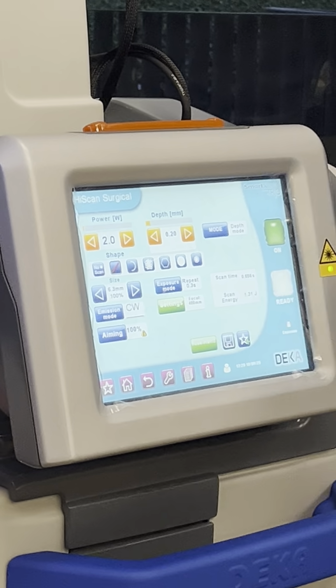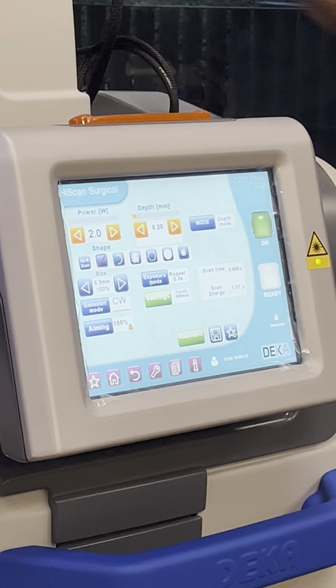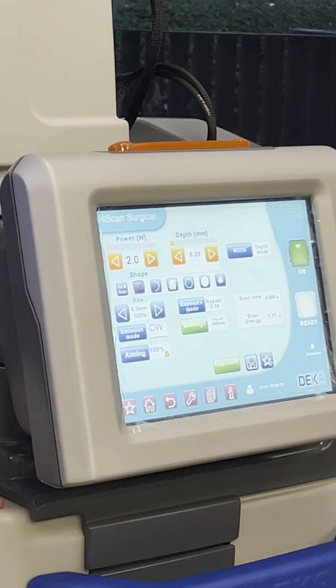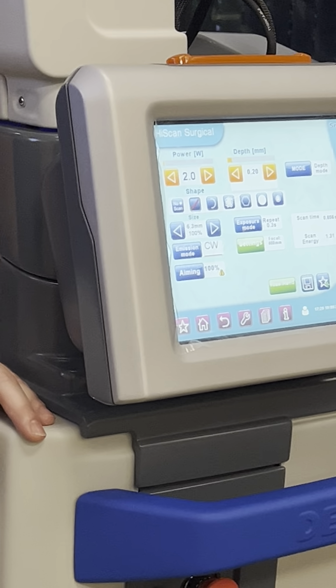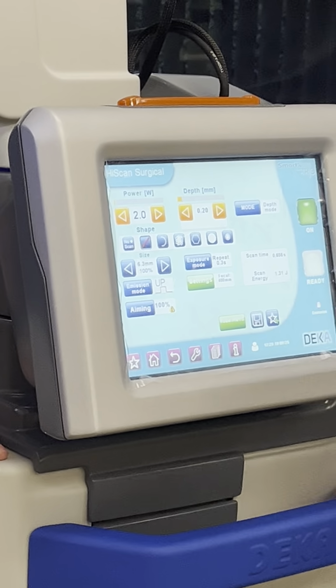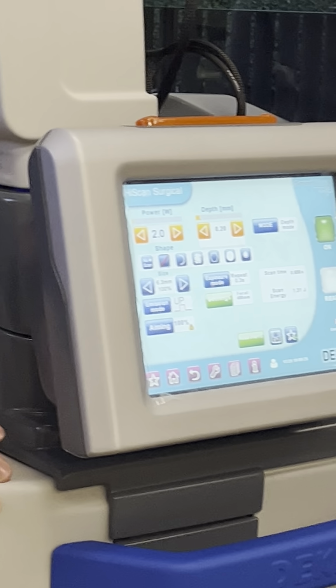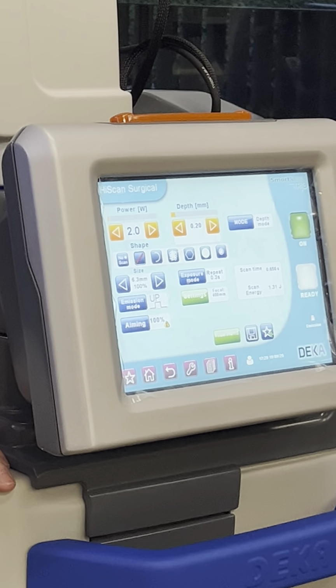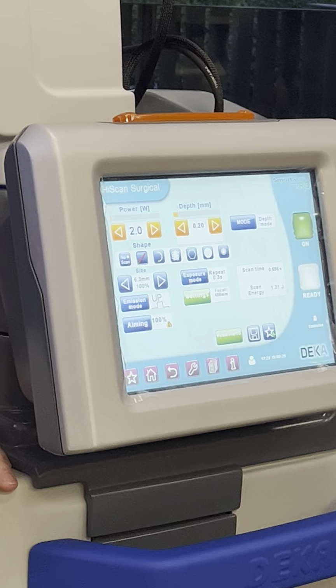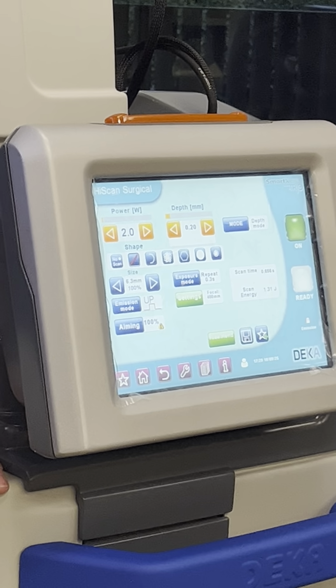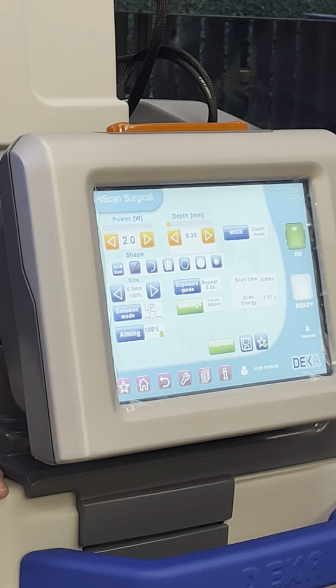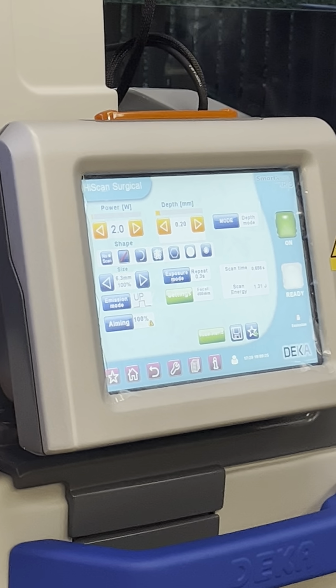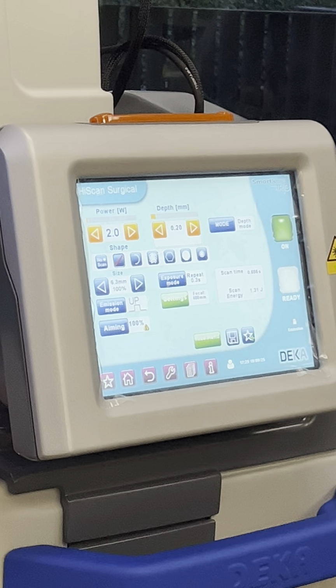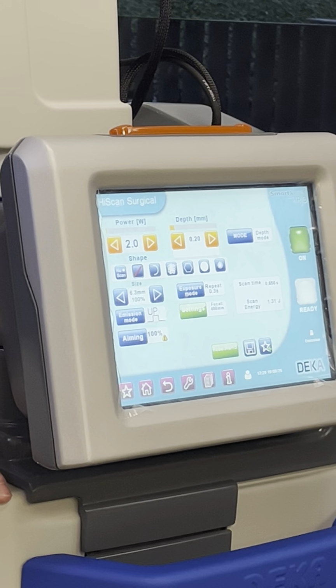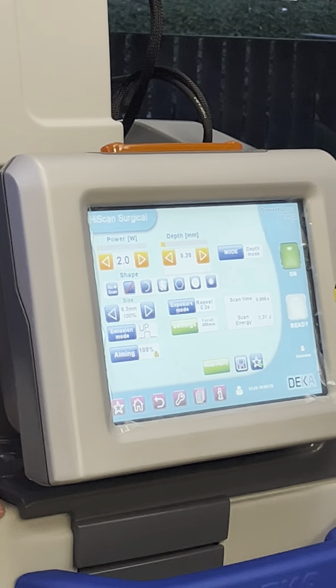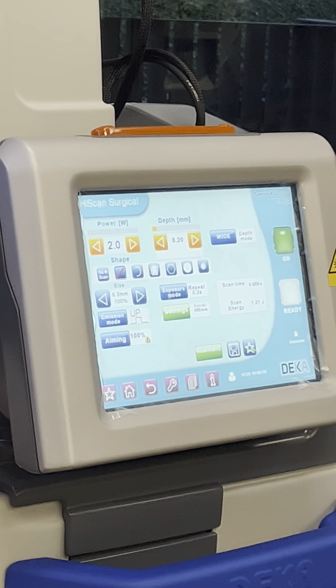Emission mode. Emission mode is how the laser energy is actually being made inside of the machine, coming out through the end. Okay, we're running on time. Ultra pulse, that's UP, or continuous wave, CW, two different things. Continuous wave is a constant Star Wars death beam coming out of the laser. Ultra pulse breaks that beam up about 10,000 times per second to allow what's called thermal relaxation time. It gives the tissue some time to cool, so you're not going to end up with a lot of charring effect.